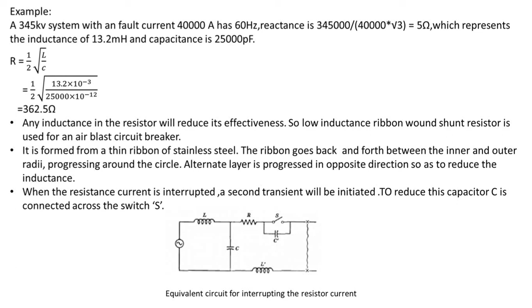Any inductance in the resistor will reduce its effectiveness. So a low inductance ribbon-wound shunt resistor is used in air blast circuit breakers. It is formed of thin ribbon of stainless steel. The ribbon goes back and forth between the inner and outer radius, progressing around the circle. Alternate layers are wound in the opposite direction so as to reduce the inductance. When the resistance is interrupted, a second transient will be initiated. To reduce this, a capacitor is connected across a switch.